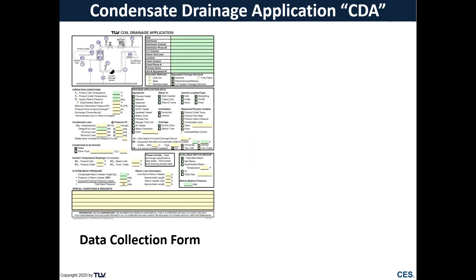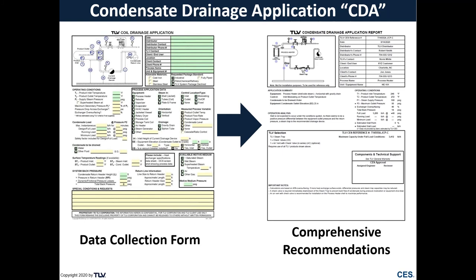Now, with all that to consider, we don't want to have you burdened with sizing and selecting steam traps for process applications and getting that wrong. So we want to be able to help you do that. TLV has what we call a condensate drainage application form. We can send you this form. You provide us with the operating conditions of your process heating equipment, and we will provide you a recommendation with important notes about that application, how that steam trap or power trap should be installed, and things that you need to consider when draining that equipment. This is something that we do as a service to you to make sure that you get that piece of equipment right and operating optimally.